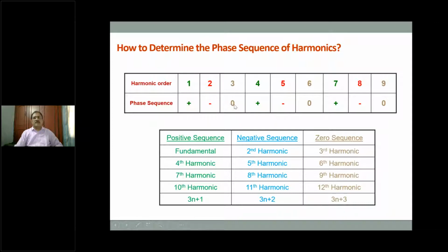The third order harmonic is called zero sequence, or triplen harmonic. You will come across the name of zero sequence as triplen, TRIPLEN, also. Fourth order, again, is a positive sequence but not counted. Fifth order is negative sequence. Sixth order is again a zero because it's a multiple of 3. Seventh is positive. Eighth is negative. Ninth is again a zero sequence.